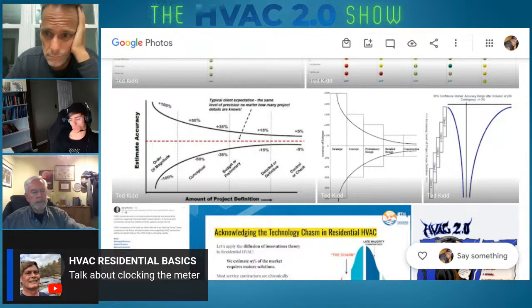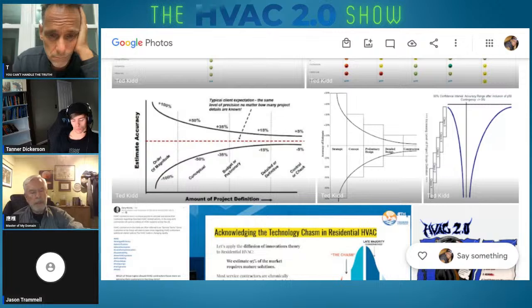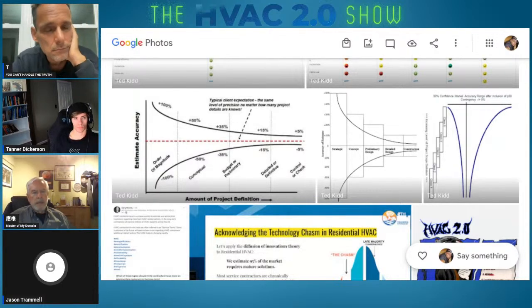That's more like commissioning of the equipment. It needs to be set up and commissioned using Measure Quick, which is the way I'd prefer to do it, and the guided workflows will work you through all of that. Once you get the equipment set up and working the way it's supposed to, it's going to do whatever the manufacturer says it'll do, as long as everything's within their specifications.